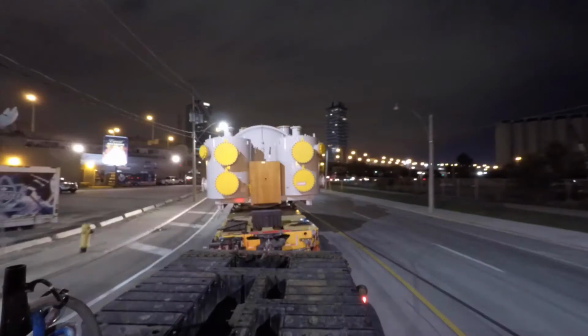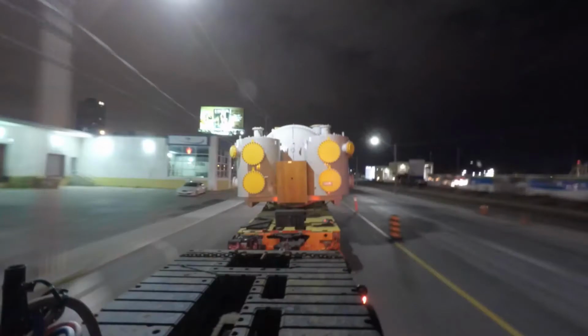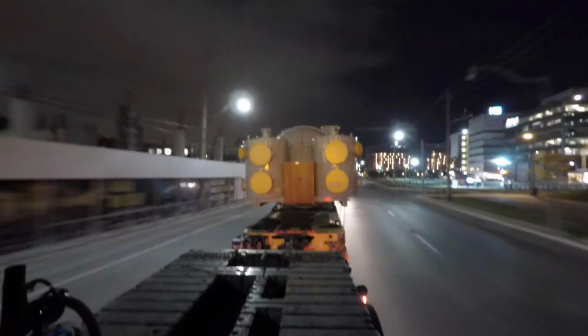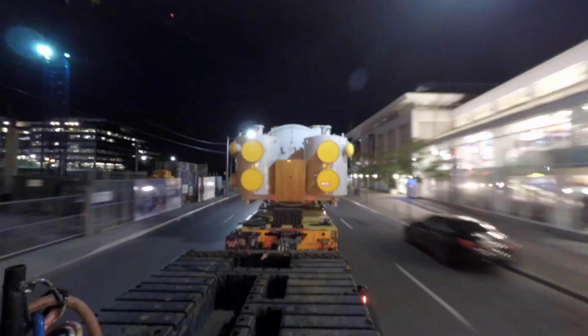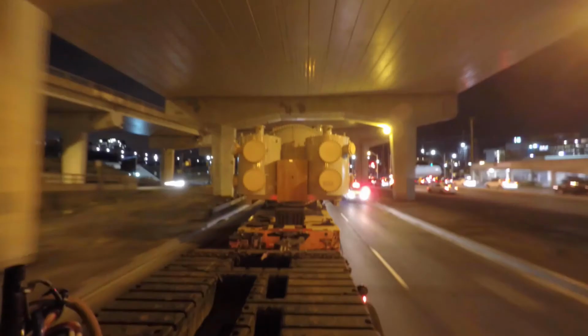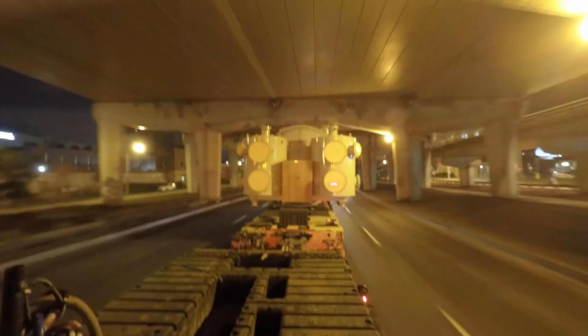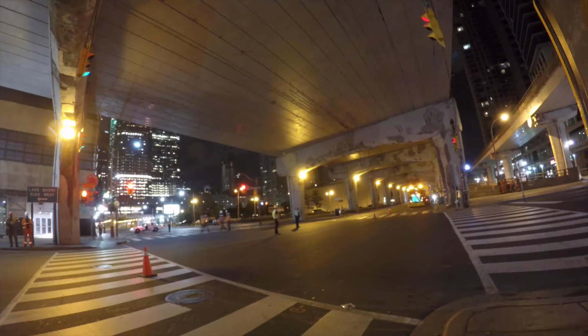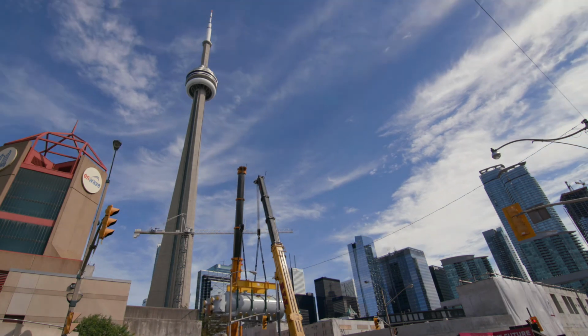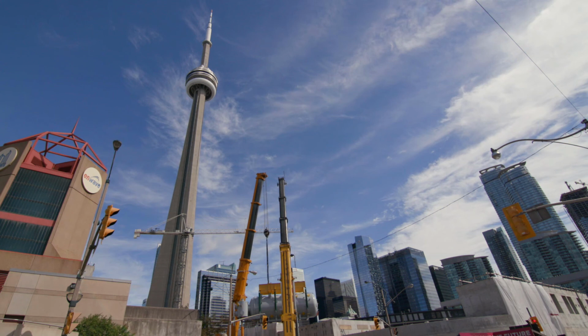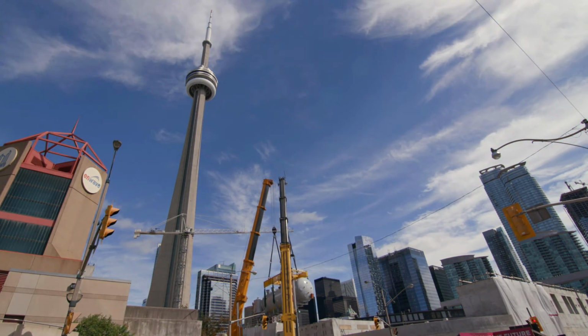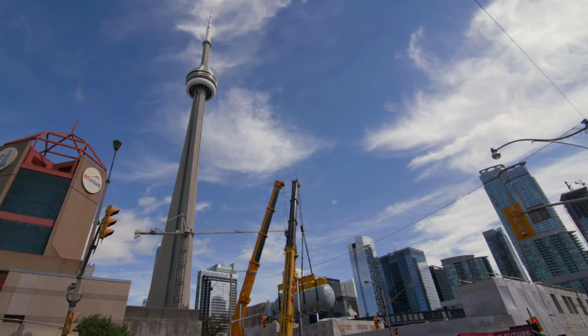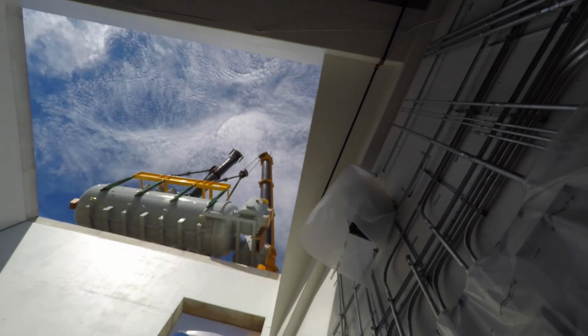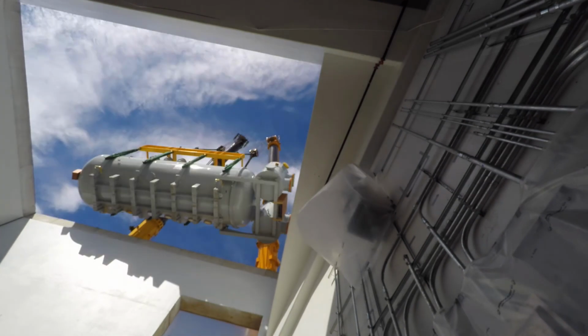In the province of Ontario, you cannot have a load without engineering. You cannot have a load over 85 tons. So we chose a route that did not go over any structure. However, in the 11th hour, we were planning a May delivery. In the 11th hour, the Toronto Transit Commission indicated that we were actually traveling over an underground LRT tunnel that they had concerns about. So we had 18 engineering studies done about the transit of our transformers over this tunnel.